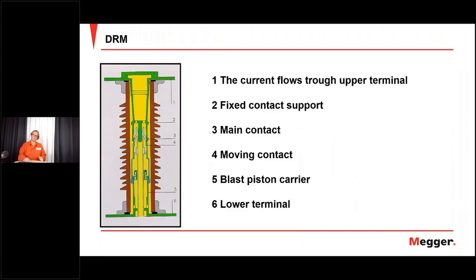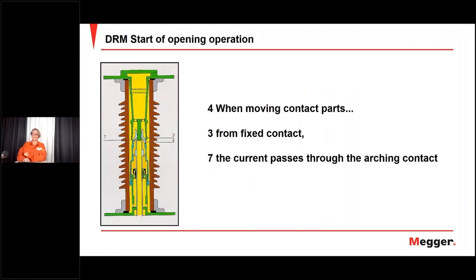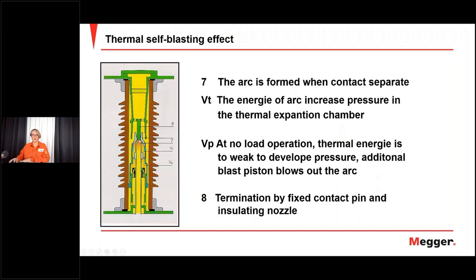So what's happening? What is it we want to see, and how does it work? Yeah, the current goes through the main contacts, over to the moving contact, and through the arcing contact in the middle. And here you also see the nozzle, the blue grayish part here. The circuit breaker starts the operation, doing an open operation, and the main part has separated here. So all the current is now flowing through the arcing contact. And now the whole circuit breaker has released mechanically, but the current is still flowing because you have the arcing going on between the arcing contacts. And the gas will now also help to blow out the arc in this closed compartment.